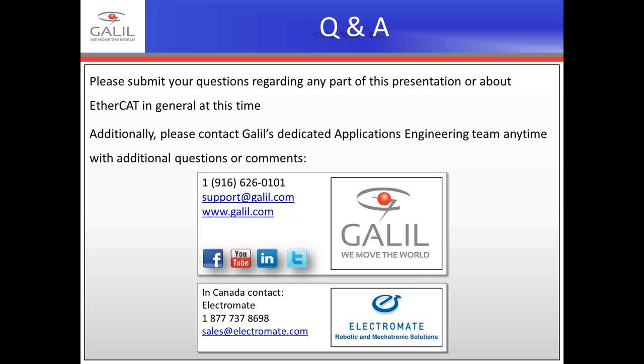Next question: My application uses a combination of electrical and hydraulic servos as well as two low-power stepper axes — how is this addressed by EtherCAT connectivity? Since the EtherCAT standard defines where profile data is written to, the type of motor actuator is transparent to the master. You can tell a servo, stepper, or actuator to move to a position. Specifically, the DMC-50,000 adds flexibility by offering simultaneous control of EtherCAT axes as well as local axes, whether stepper or servo, including low-cost internal amplifiers, saving costs and maintenance.